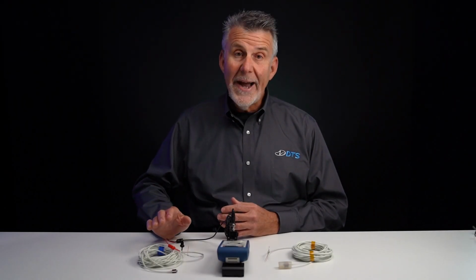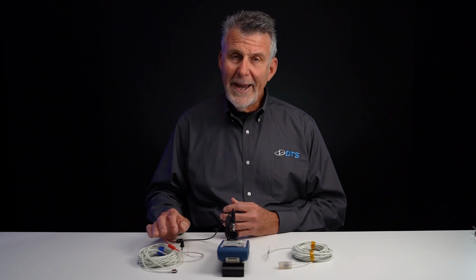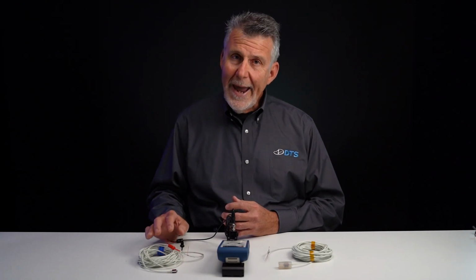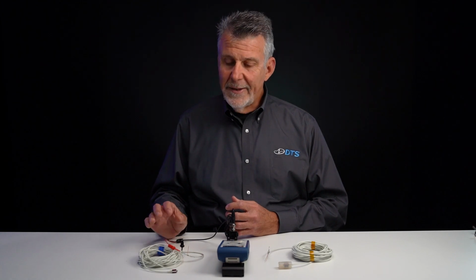Based on the fact that the diagnostic readings we just took with the multimeter indicate an imbalance in the bridge of this sensor, and it failed the diagnostics checks in the software, it's pretty safe to conclude that this sensor is broken and needs to be replaced. It's important to note that if you have a suspected bad sensor, you should check the sensor manufacturer's data sheet and any available calibration reports. Those documents often contain information about the expected resistances that you should find on the bridge or the sensor output. If you compare those numbers to the measurements that you take with the multimeter, that might also help seal the deal that you do or do not have a bad sensor.